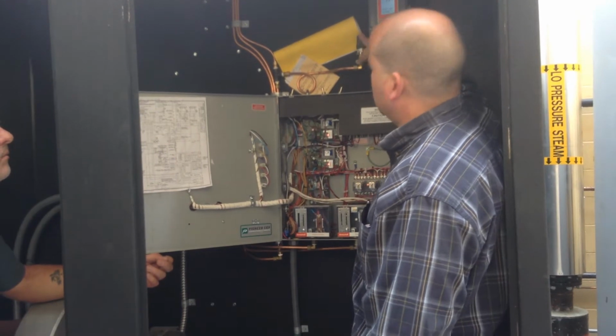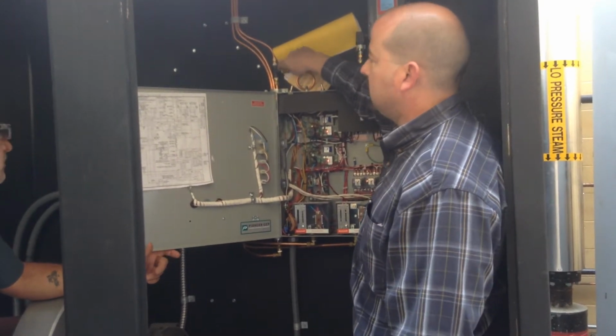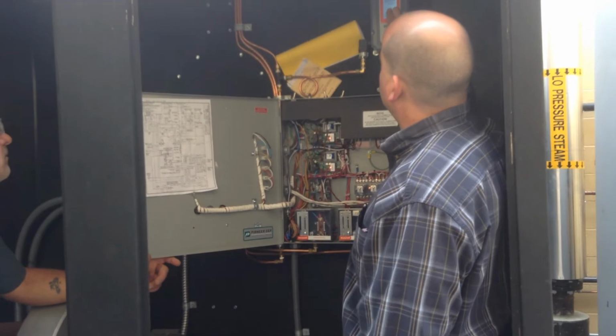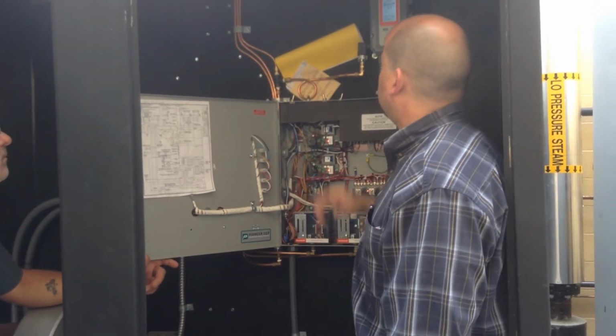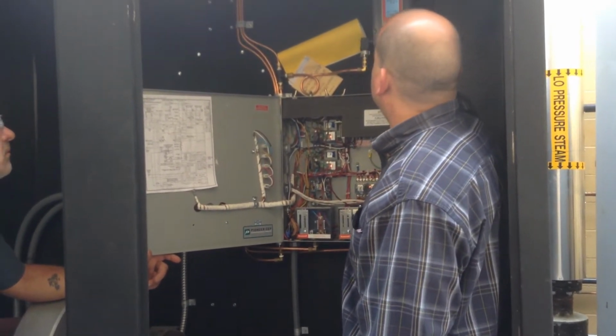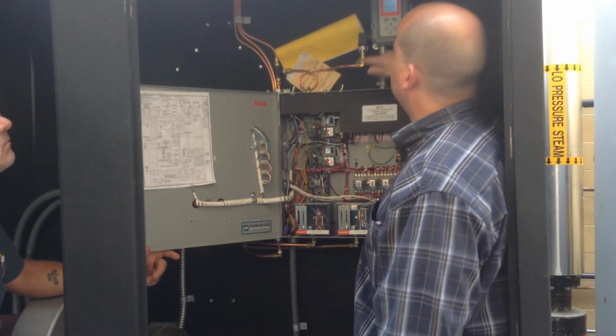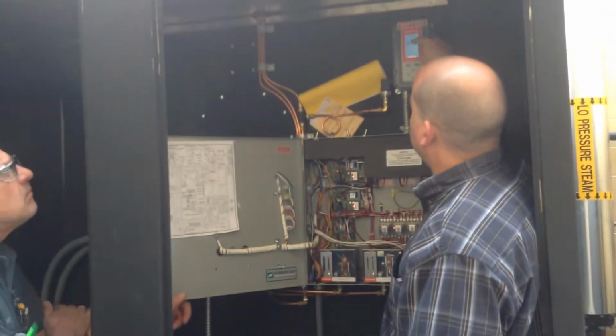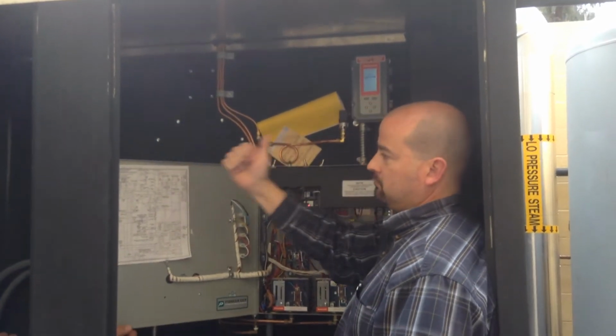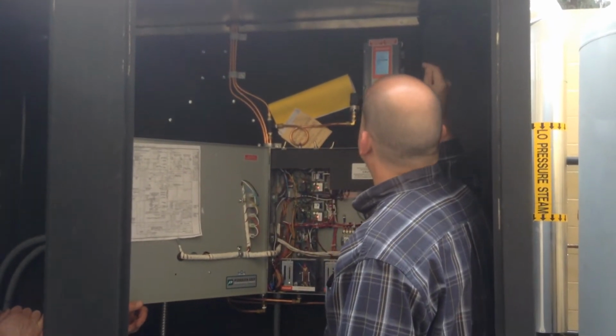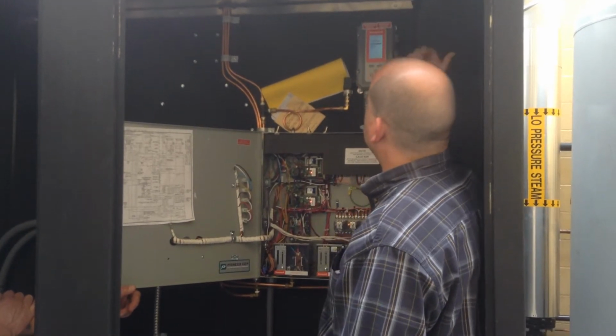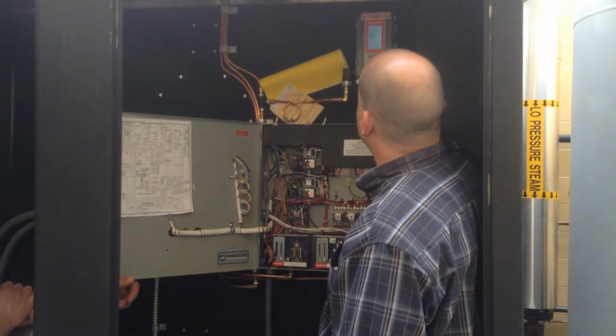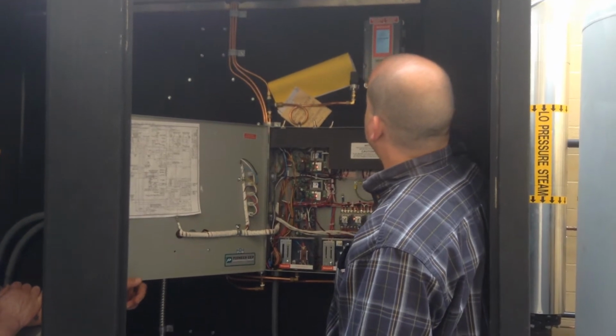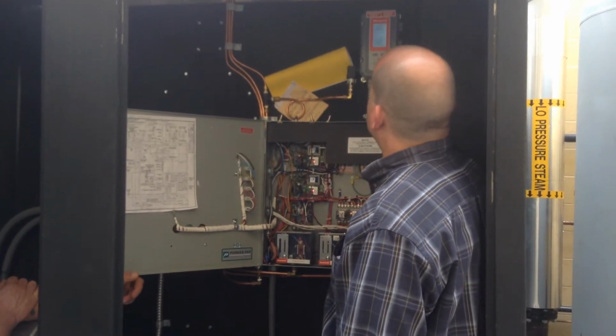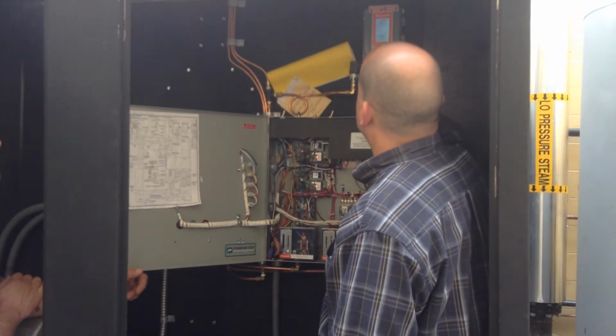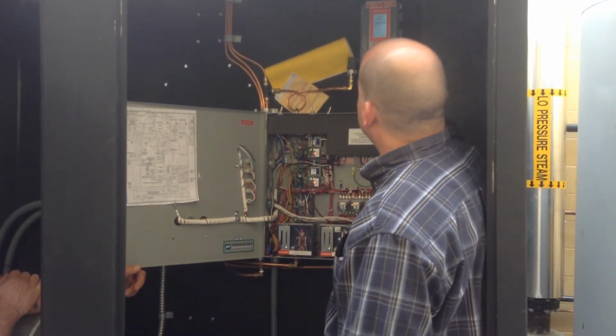This has a pressure transducer, which is right here, measuring the pressure in the boiler. So right now we're at 3.5 PSI. I don't know what it's set for, but it's actually pretty intuitive. If you want to change anything, you can hit menu, and then it goes automatically to program, and it's telling you to go that way with the arrow. And then you have your modulating signal. When we tell it to modulate down, you can go down to relay 1. And you have your set point, it's telling you to go that way on set point. So it's set for 10 psi, that's what the pressure is. And then if you ever just want to get out of it, just hit home.